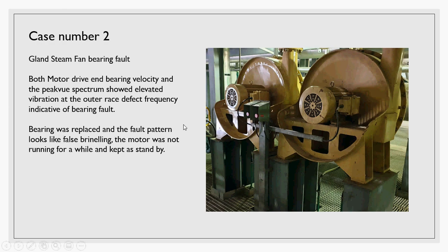Today I'm going to talk about this case of a Gland Steam Fan bearing fault. As you can see in the photo, we have two Glant Steam Fans — a motor direct coupled with the fan. One of the machines is running and the other one is kept on standby. What happened is the vibration kept being transmitted from the running machine to the standby one, causing this bearing defect problem.